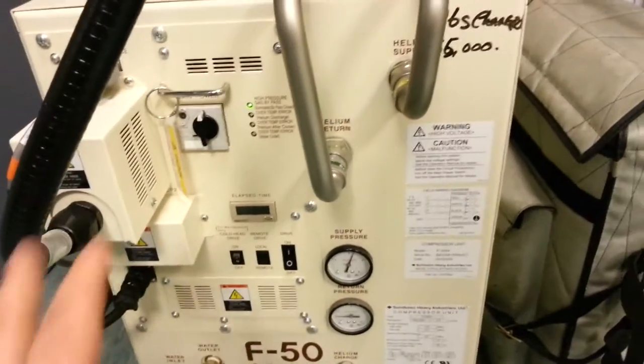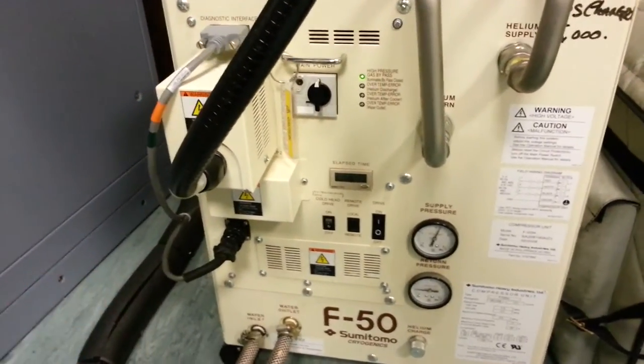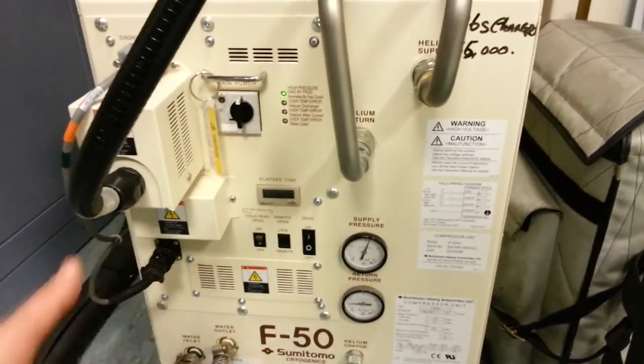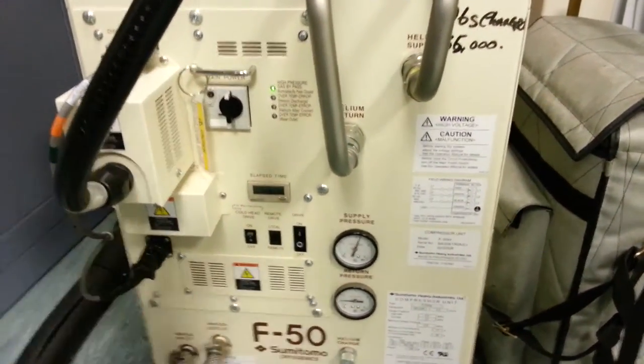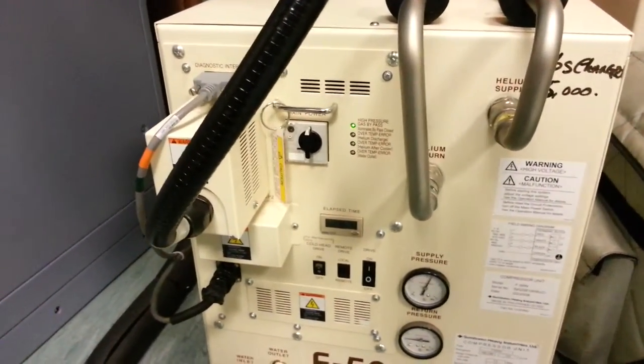You can tell immediately this is an unusual refrigerator — to use helium as the refrigerant gas and not one of the conventional refrigerants. This is quite a complicated compressor, but of course it's a bit more than a compressor. It's a compressor and a condenser — well, obviously it's not a condenser in this case because the helium doesn't actually liquefy, but it does the same job as a condenser.